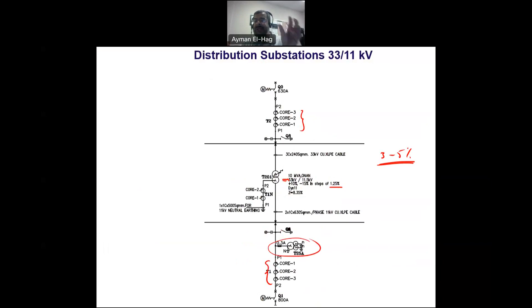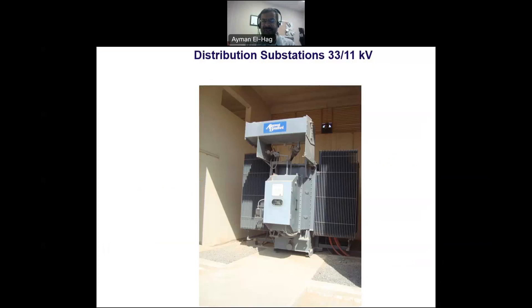Let's look at the physical structure of the transformer. This is the 10 MVA transformer. At the top we see the conservator. Whenever the transformer oil gets heated, it needs to expand, so it goes up here. When the transformer cools, the oil goes down. This gives you room for the expansion and contraction of the oil.